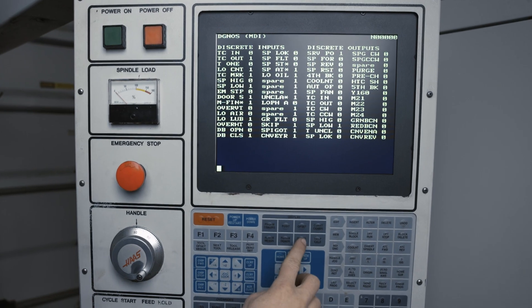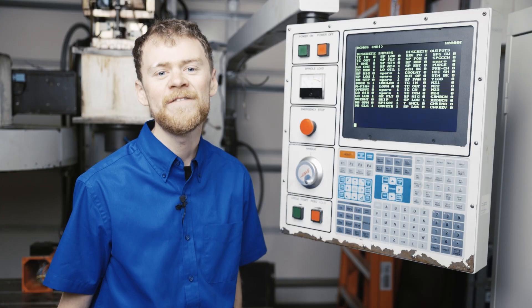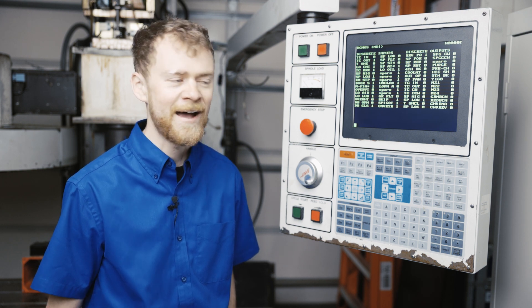To start with, you're going to need to go to setting 7 and disable the parameter lock. Then you're going to want to go to parameter 57 and disable the gearbox. But don't do that without first checking to be sure that you're in high gear.